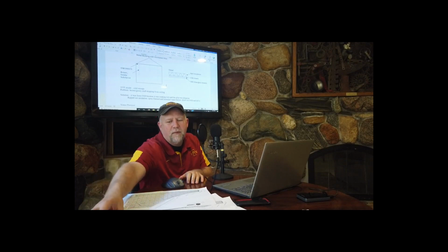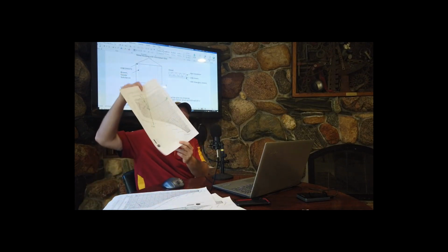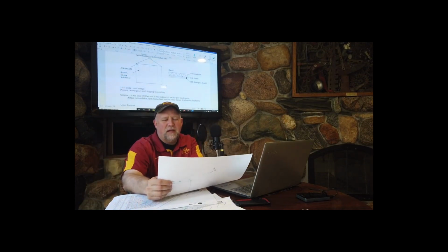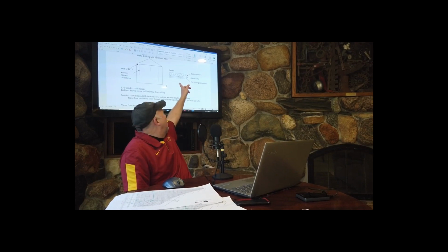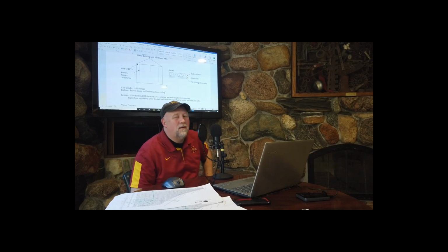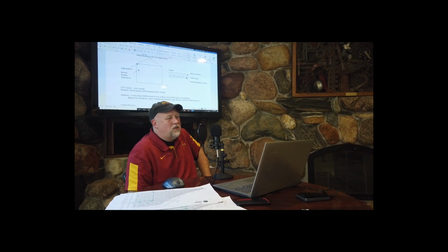Well, if we grab your Psych chart, and if we look at 95 degrees, 50% relative humidity, dew point is at 73.5 degrees. If it's 35 degrees in the area where they're working, and 95 up here, 75 is going to happen somewhere in the middle of that insulation.